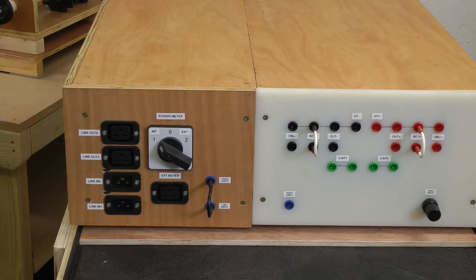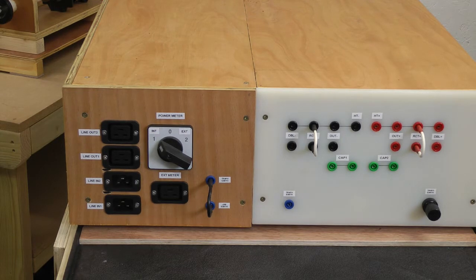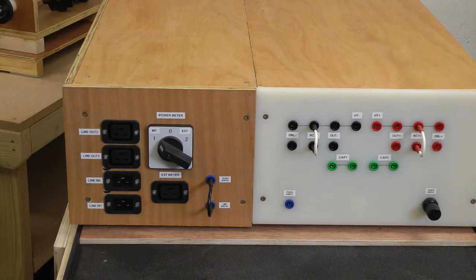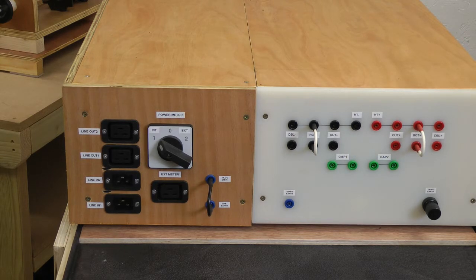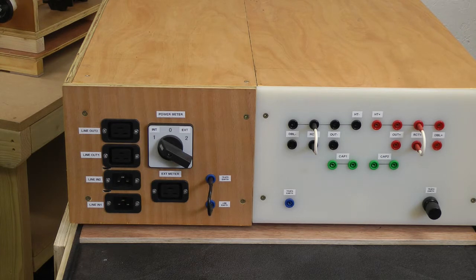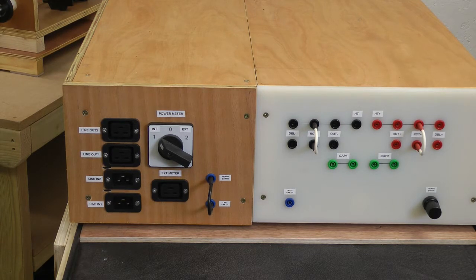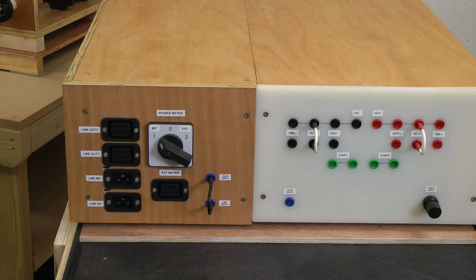This plate supply, if you were using all 3 transformers in series and you were using the doubler or the level shifter, as it should probably be called, then open circuit with all that going flat out, you'd be up to 18 kilovolts. So obviously all the necessary precautions need to be taken care of. If you're running all 3 transformers in parallel without the doubler, then you're down to somewhere around about 2 kilovolts at about 2.5 amps. So the nominal rating of this is all the way from 2 kilovolts at 2.5 amps up to around about 15 kilovolts at 200 milliamps, by various arrangements of the transformers and using the various internal systems like the level shifter.